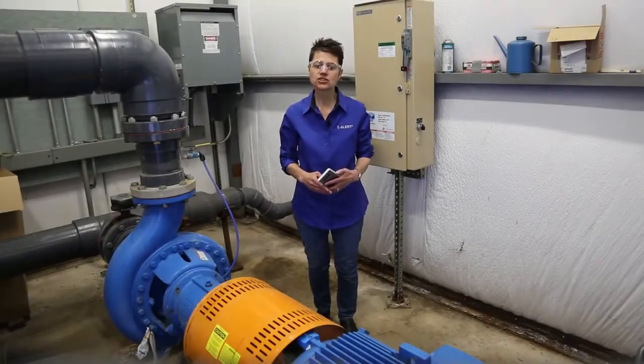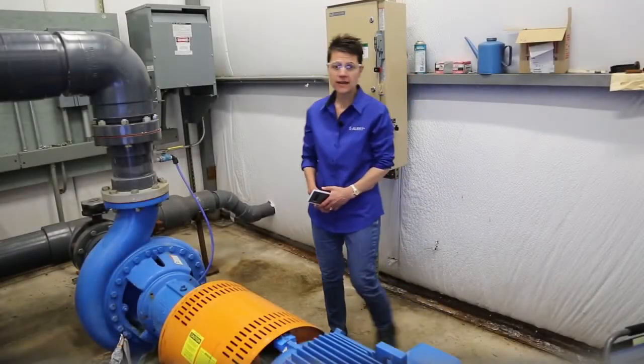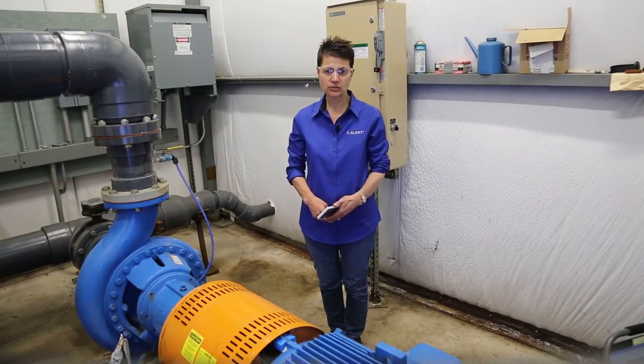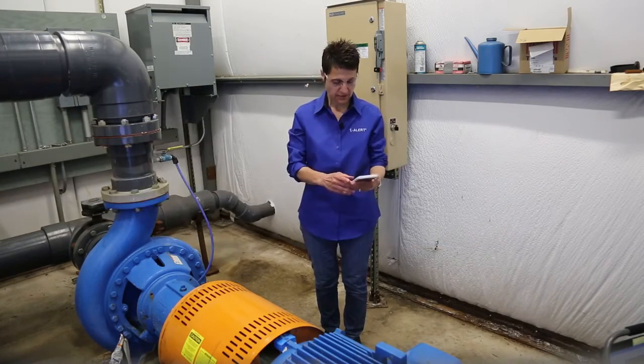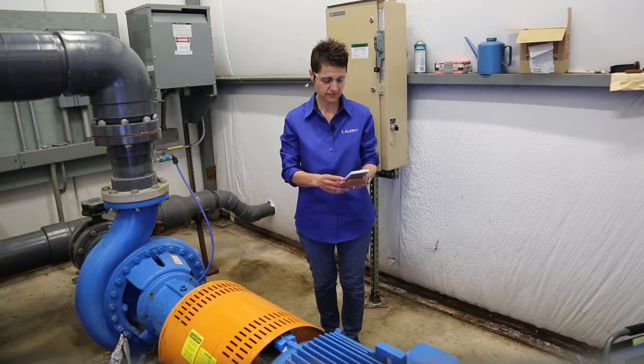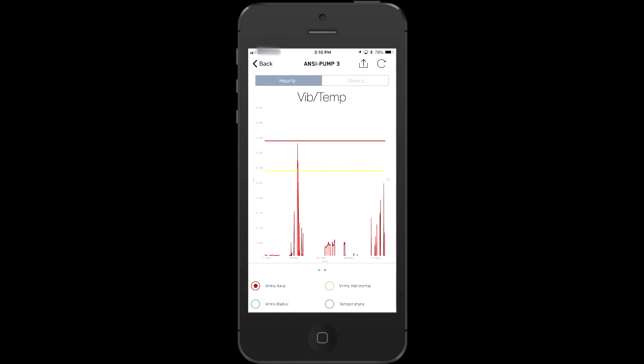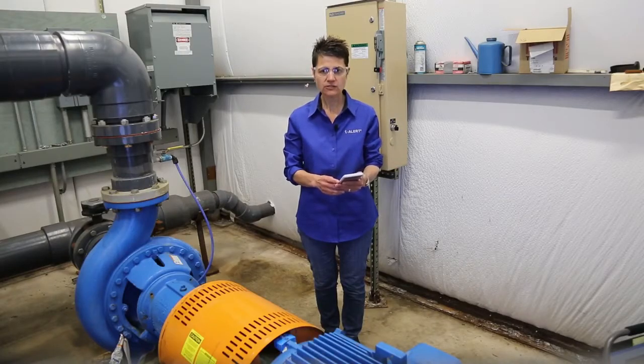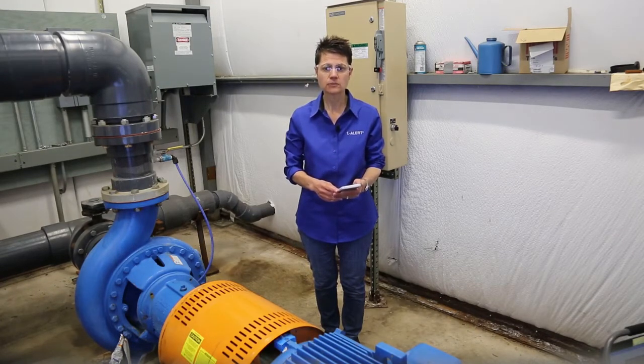I will let the newly sensored machine run for a few weeks and see the kind of data it collects. Okay, we're back, so let's take a look. We see our machine is running normal but is showing an alarm condition within the last seven days. Here's the dashboard that tracks overall vibration in all three axes, the temperature, the runtime, and the battery life of the iAlert. Here's all the trend data you've never been able to see before. Oh, and what's this? A spike. It happened last Tuesday at 2 a.m. You know that because everything has a timestamp, and that's really powerful.